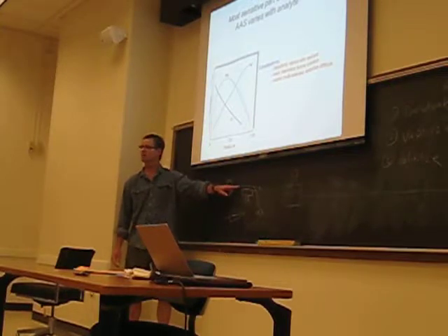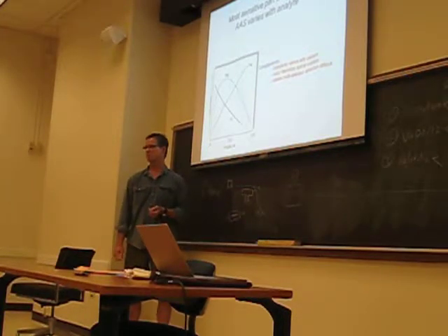And you can go in, once the flame's on and there's a dial, I'll show which dial it is, and you can raise and lower that, and you can see, is this really optimized? And for copper, it'll be one place, and for lead, it will likely be a different place. Slightly different. So that should be done with every element. Every element is slightly different. And that's what this is meant to show.